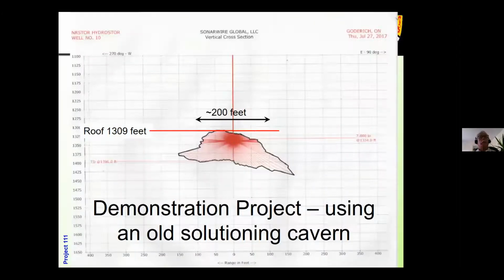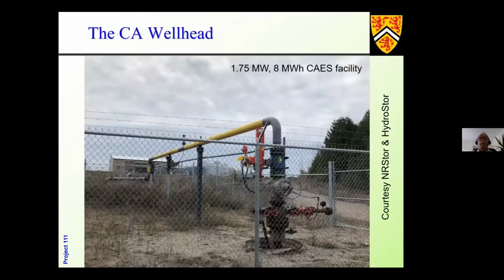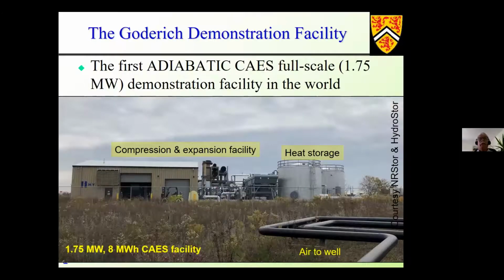So this is just a cross section of the salt cavern from sonar. I would never use an old solution cavern if I had the privilege of building a cavern in a good shape so that it's geomechanically more stable. This is the wellbore where compressed air goes in and out, and this is the facility in the background. The compression and expansion is on the left, and those tanks store the compression energy, the heat of compression, in a thermal oil.